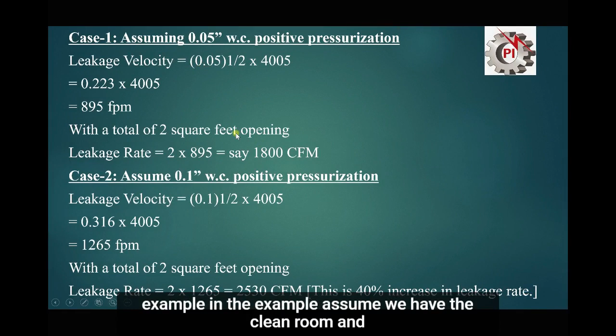In the example, assume we have a clean room with positive pressure of 0.05 inch of water gauge. First we will find the leakage velocity. Using this formula, we just put in the values and the result is 895 feet per minute, with a total of 2 square feet of opening. It means that under the door cuts we have an opening of 2 square feet. Now we calculate the leakage rate, area times velocity. The answer is 1800 CFM.